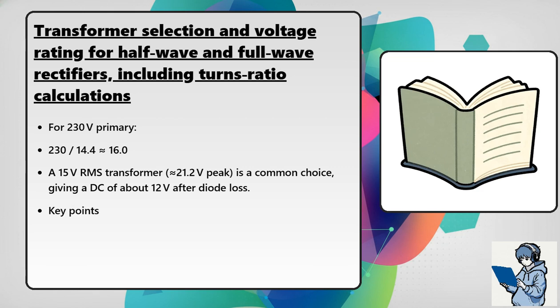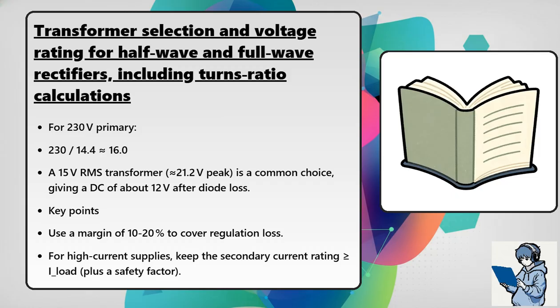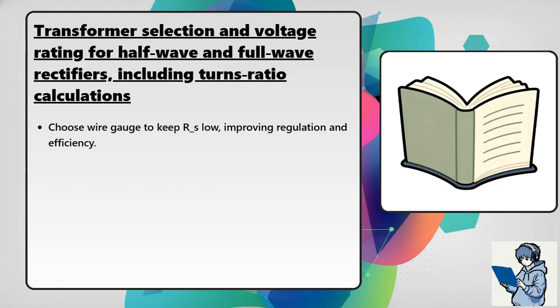The key points: use a margin of 10 to 20 percent to cover regulation loss. For high current supplies, keep the secondary current rating greater than or equal to I load, plus a safety factor. Choose wire gauge to keep R S low, improving regulation and efficiency.